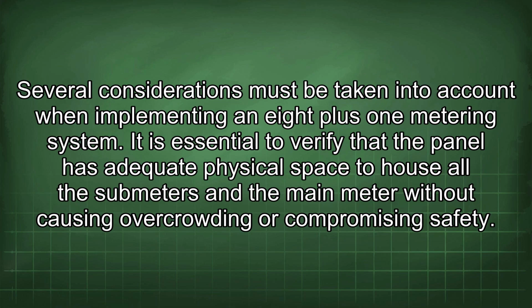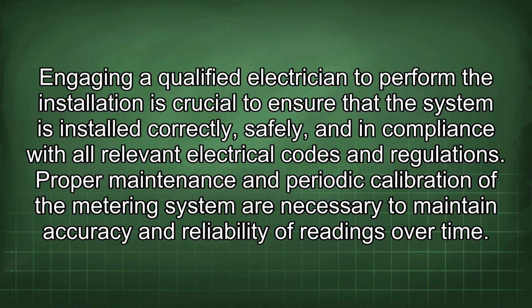Several considerations must be taken into account when implementing an 8+1 metering system. It is essential to verify that the panel has adequate physical space to house all the submeters and the main meter without causing overcrowding or compromising safety. Engaging a qualified electrician to perform the installation is crucial to ensure that the system is installed correctly, safely, and in compliance with all relevant electrical codes and regulations.